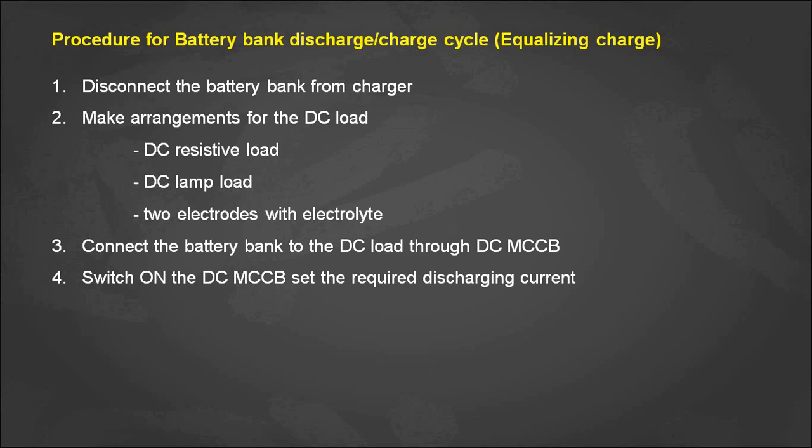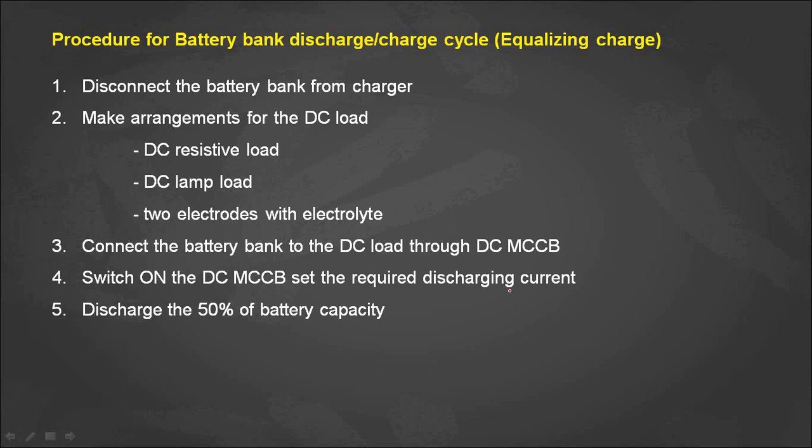After discharging up to 50% of battery capacity, stop the discharge. This 50% discharge limit is recommended so that sufficient charge remains for a healthy recharge. For example, if you have a 100 ampere hour battery bank, set the discharge current to 10 amps for 5 hours to discharge 50 ampere hours.